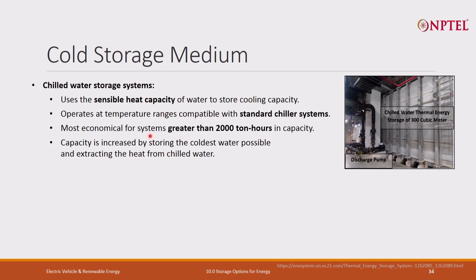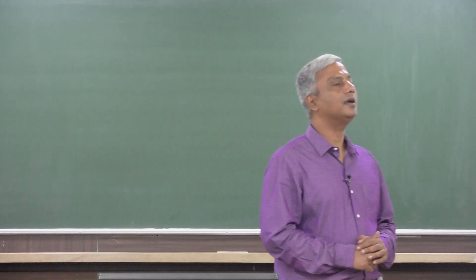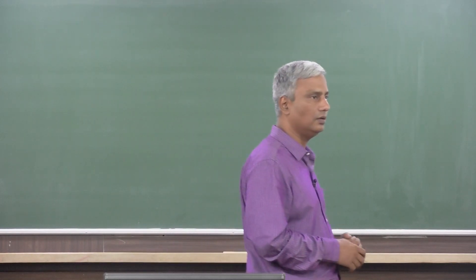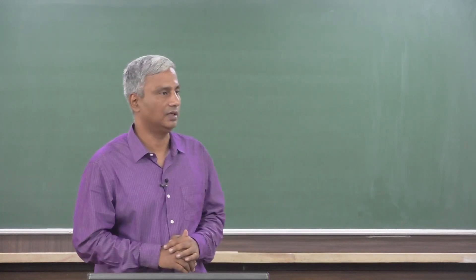The chilled water system is what we are utilizing at IIT Madras Research Park. We have a 300 cubic meter storage capacity which chills water to 6 degrees centigrade using the chiller whenever we have excess renewable energy available. We utilize this chilled water to run the HVAC system on a regular basis. Whenever I have excess renewable energy I start chilling the storage water. Our system efficiency is worked out based at 6 degrees centigrade, so we use that capacity.